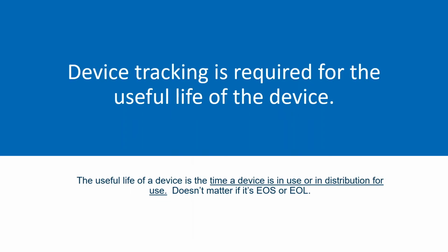Okay, device tracking is required for the useful life of the device. This is off the FDA website. I just want you to know that the FDA defines the useful life of the device as the time a device is in use or in distribution for use. Period. So even if it's end of service or end of life, the OEM still has to track it. As long as it's still in use, they have to track that system. They still have an obligation because it's still in distribution or use. So if there's a recall on it, or an adverse event happens with one of these systems, they still have to notify you of that.